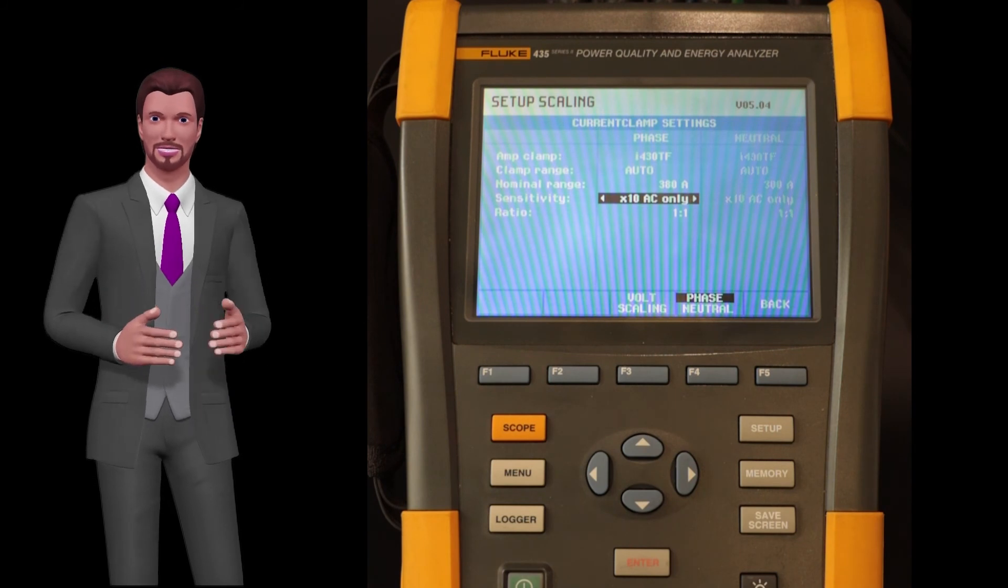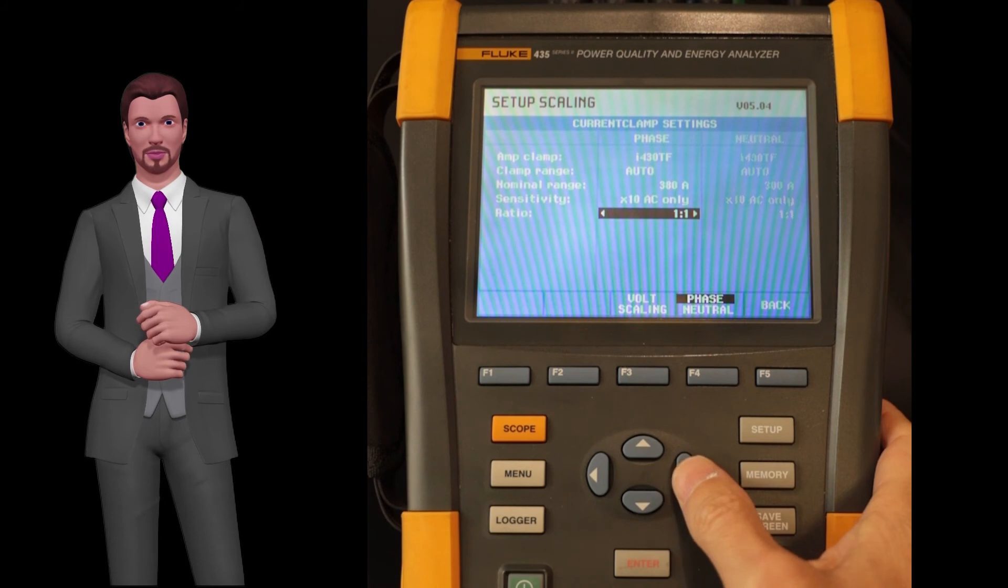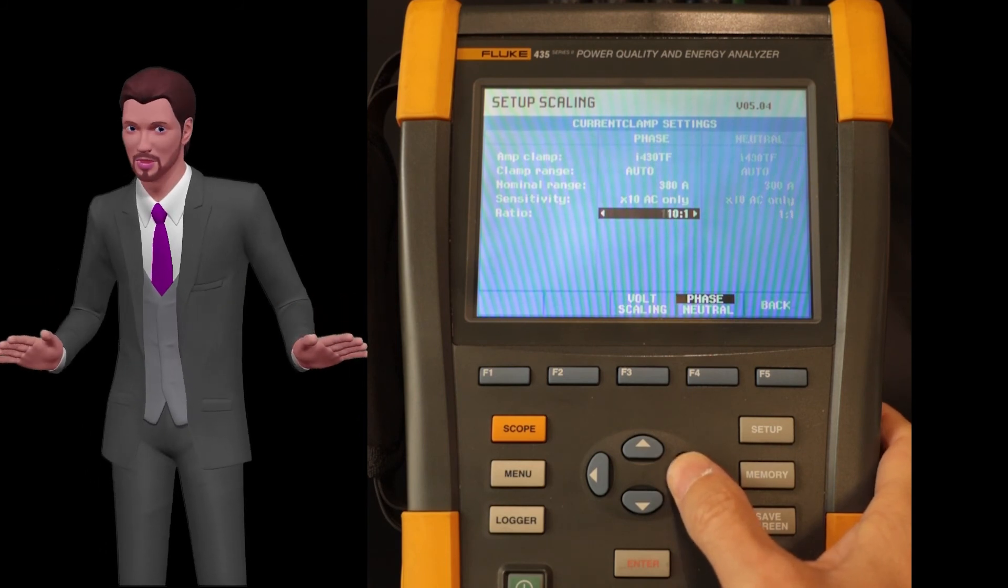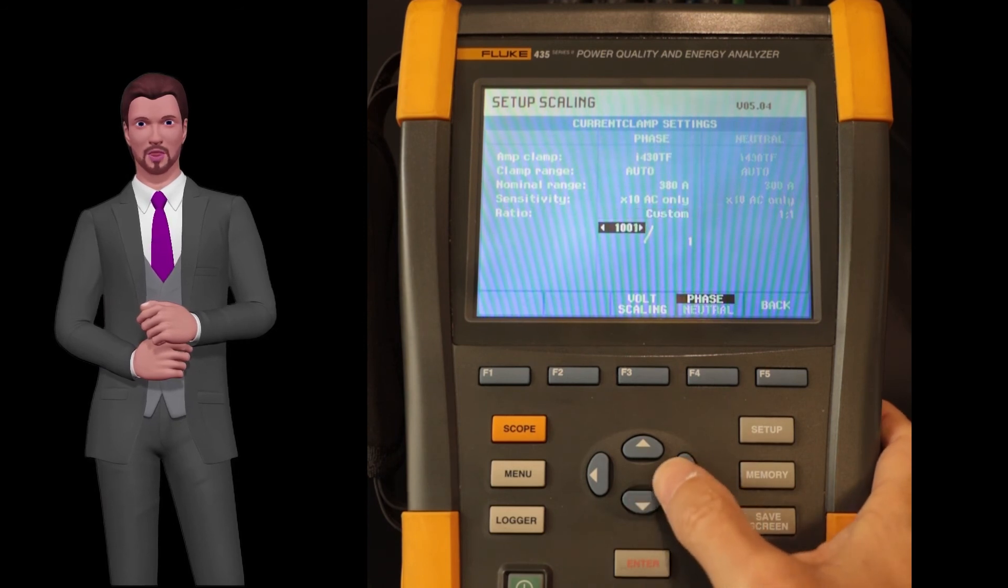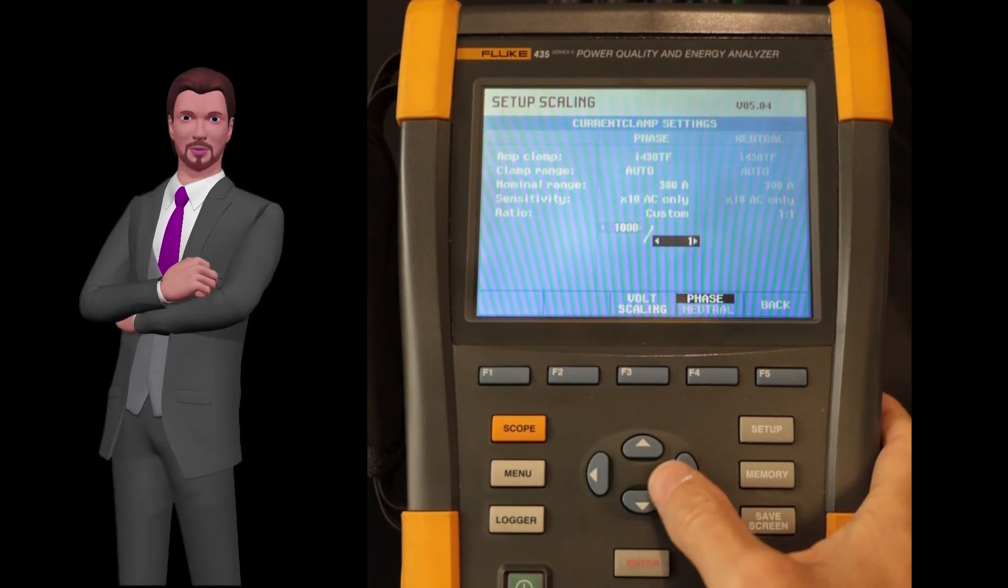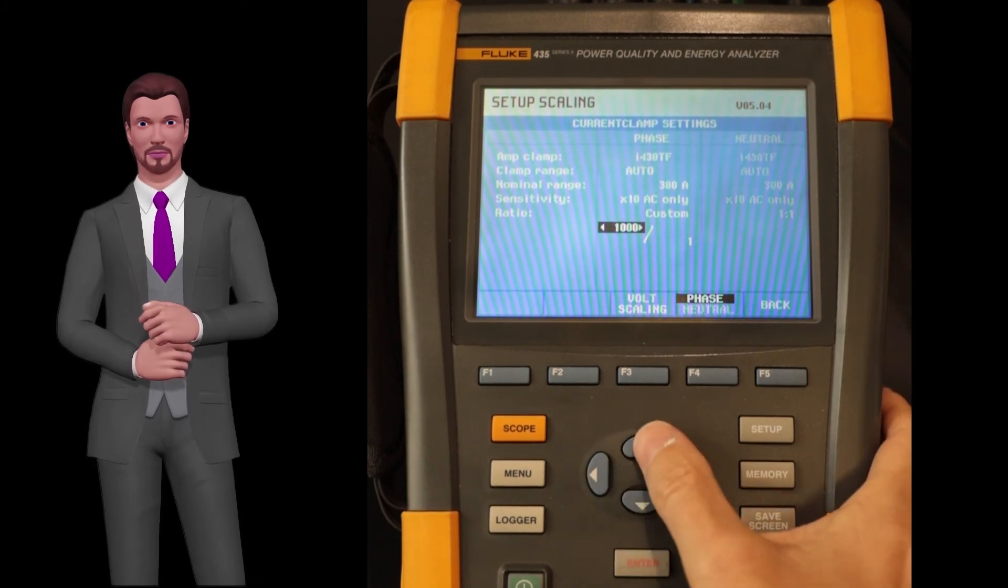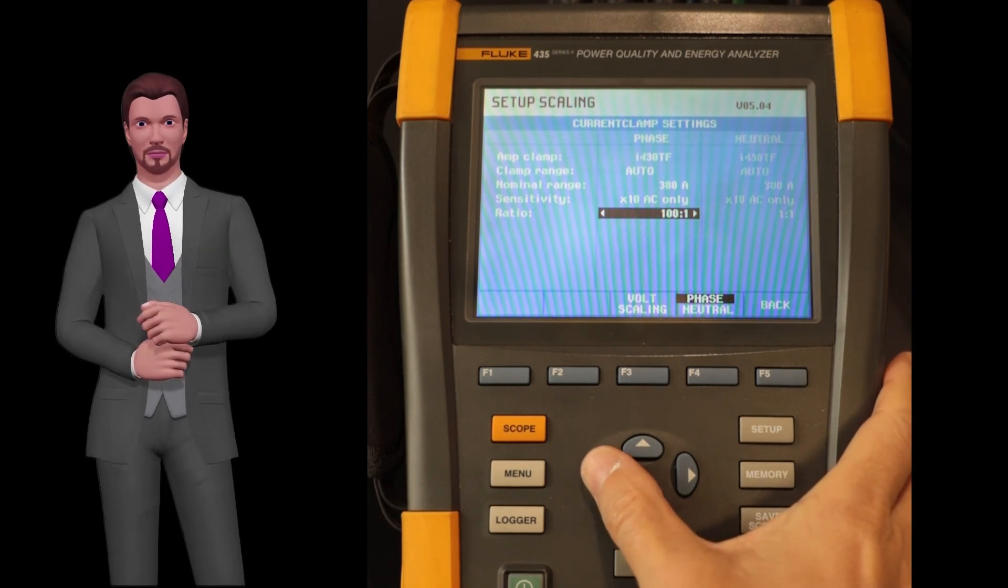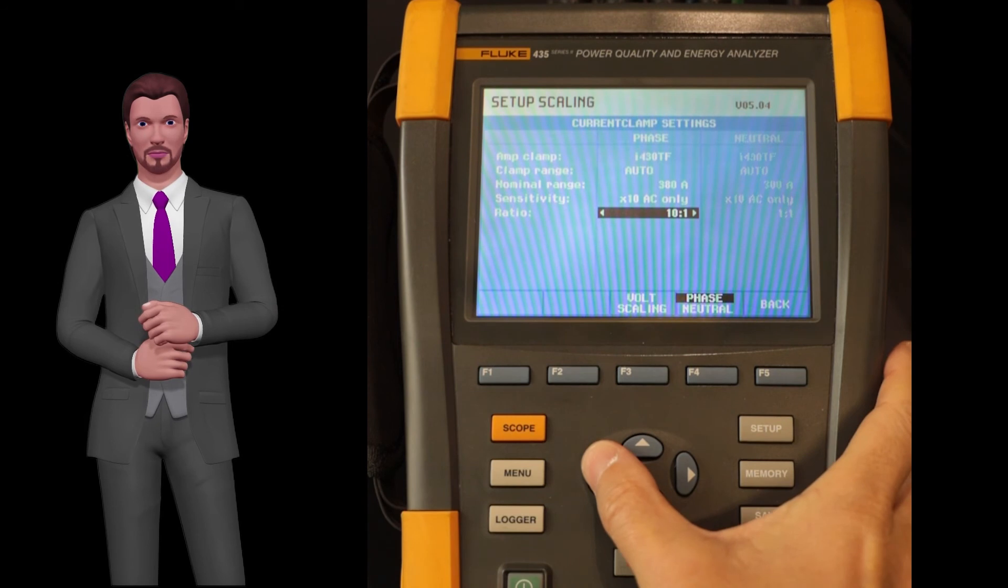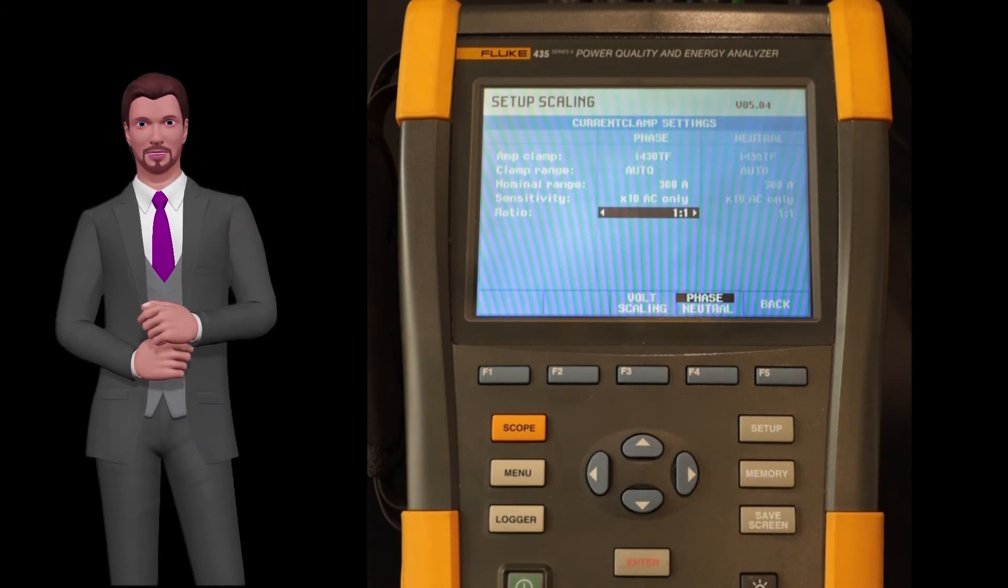Finally, with the down arrow key we select the ratio option. Once this option is selected, with the right and left arrows we can move through several options, in order to select the transformation ratio in the case that current measurement transformers are used in medium and high voltage systems, as normally happens for example in electrical substations. In this way, the unit will apply this transformation ratio to measured low voltage current at the output of the current measurement transformer, in order to calculate and display medium and high voltage current values.